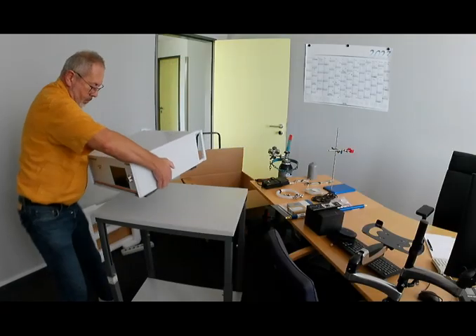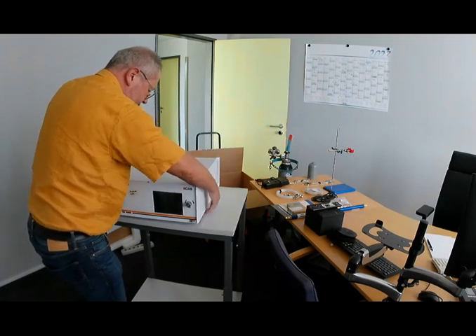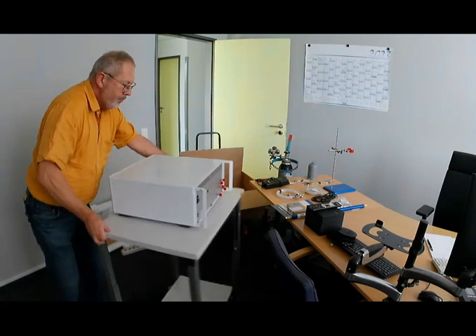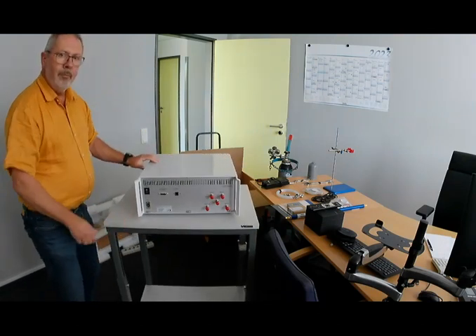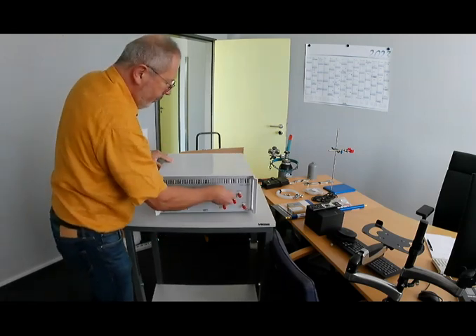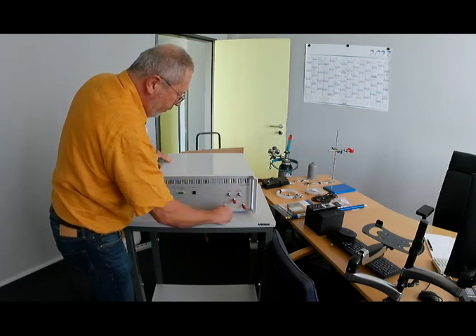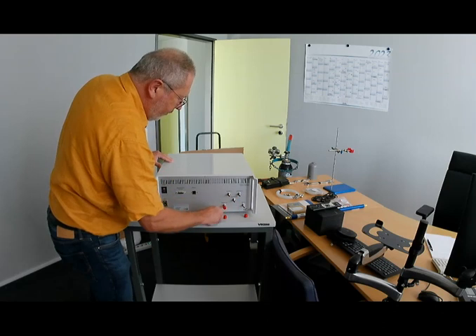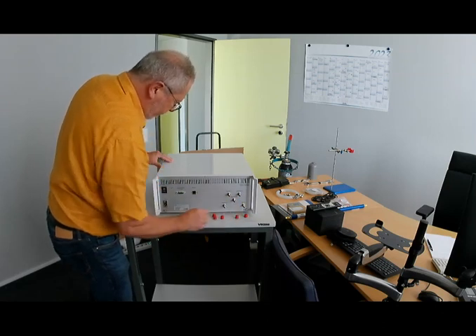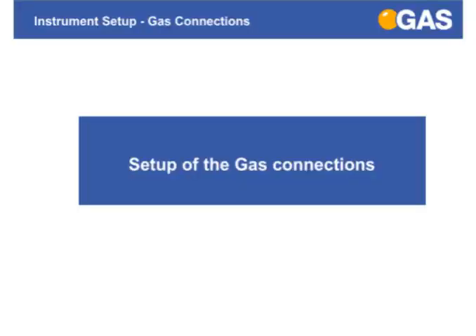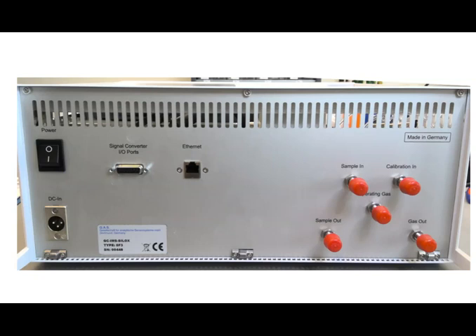We lift the instrument out of the box, place it on a trolley or on the table and have a look at the rear side of the panel. We need to remove the red protective caps. We need to unscrew them. The rear panel shows 3 gas inlet sockets and 2 outlet sockets: the sample in, the calibration in, and the operating gas inlet. The outlets are for the sample out and the gas out.